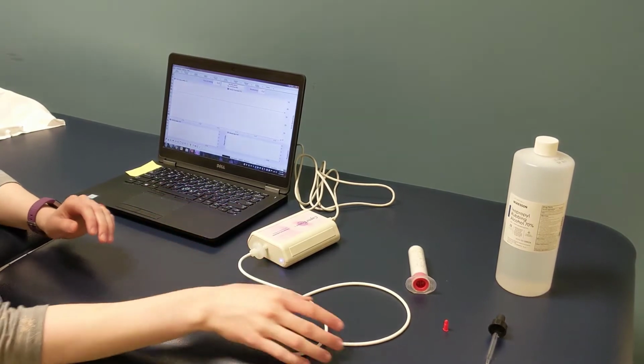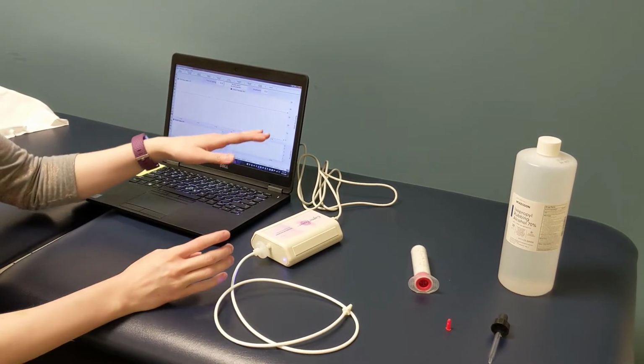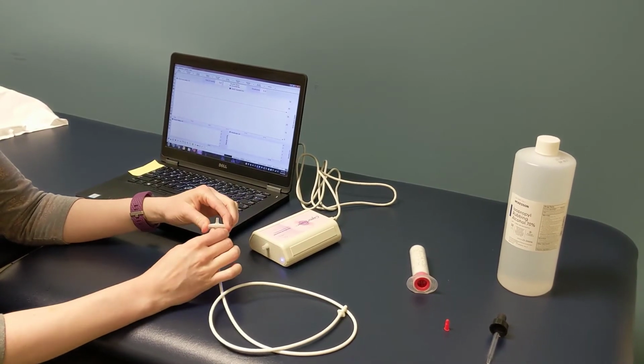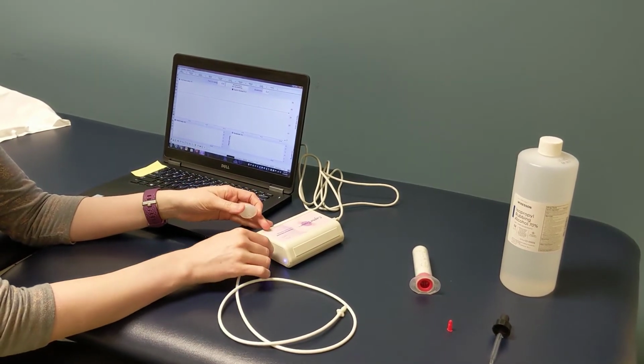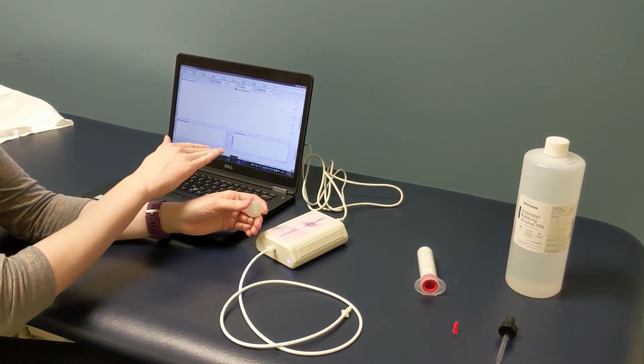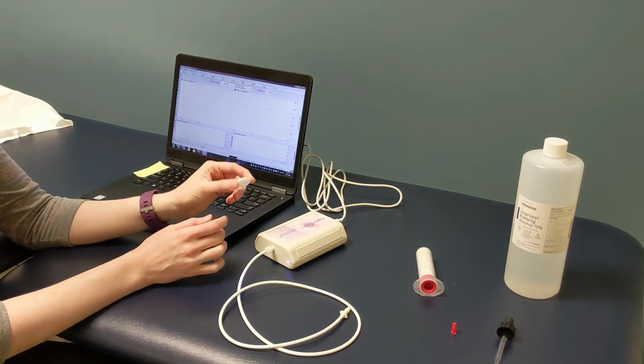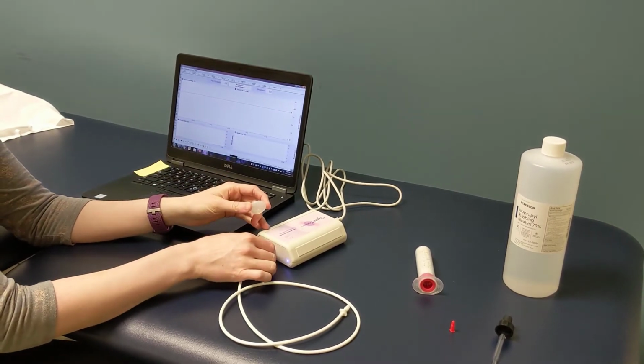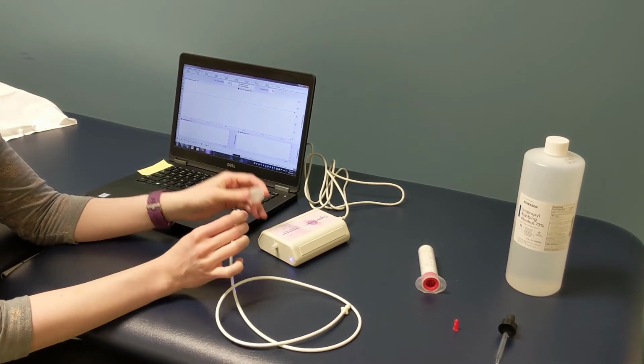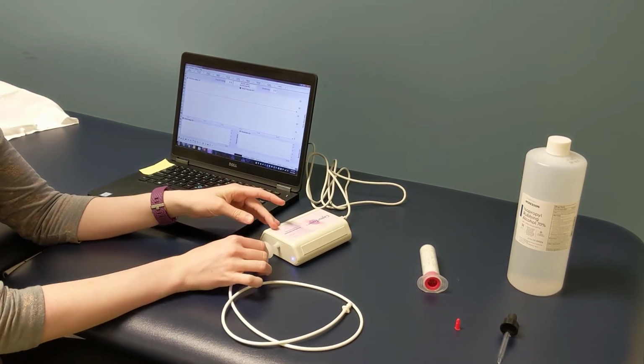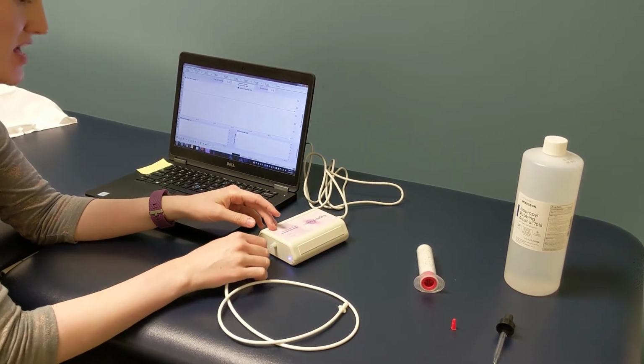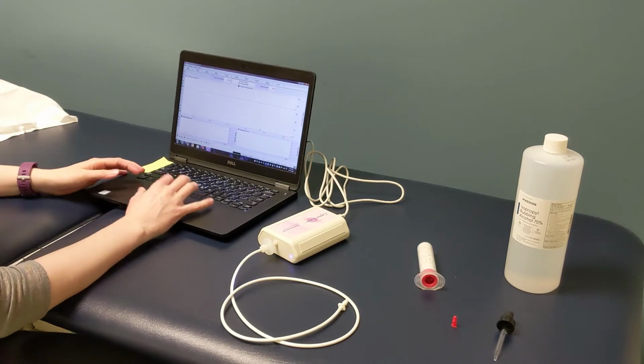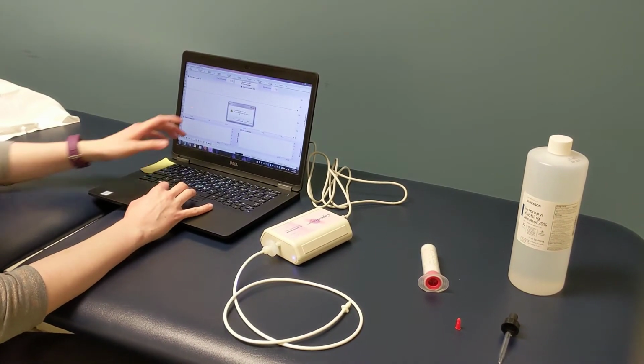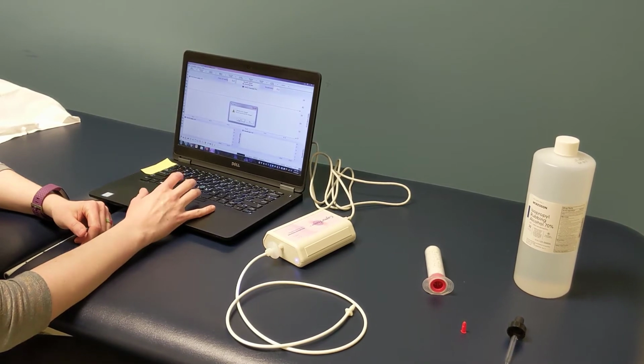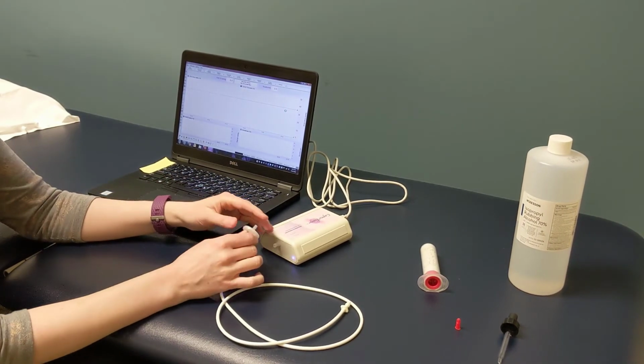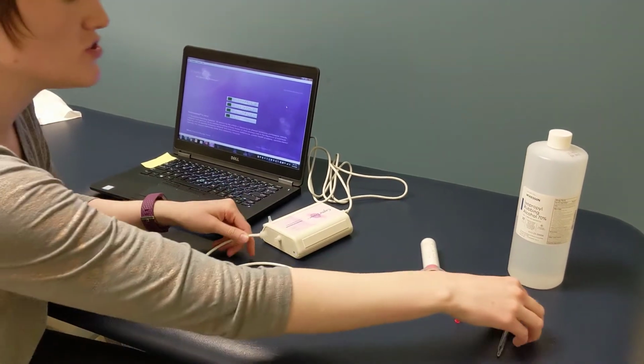If when you attach the filter back to the machine and it is still not at zero, what you can do is take the filter off and connect the sampling tube directly to the CapnoTrainer. If that is at zero, but with the filter it was not, you need to replace your filter. Okay? You never want to have a client on the CapnoTrainer without a filter. It just helps that you don't have to do this process quite so often. Now, once you have done filtering, you're going to leave, and it'll say calibration has changed. Do you want to save the changes? You press yes.